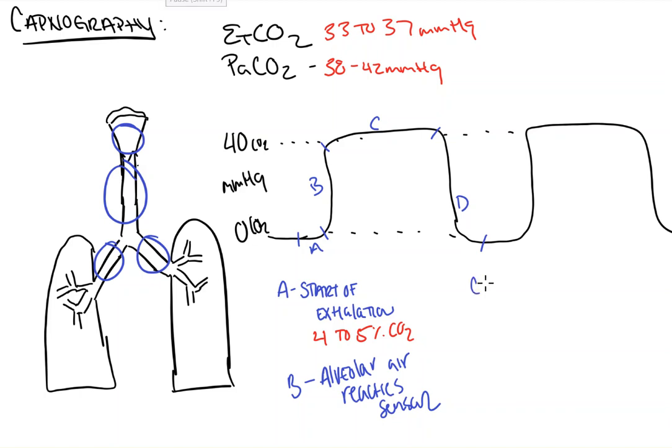Section C represents the alveolar plateau, and this is the point at which the last of the alveolar CO2 is being seen by the sensor. So, this is where it actually measures your end tidal CO2. Now, between sections B and C, there's this angle here called the alpha angle, and the alpha angle represents VQ matching.